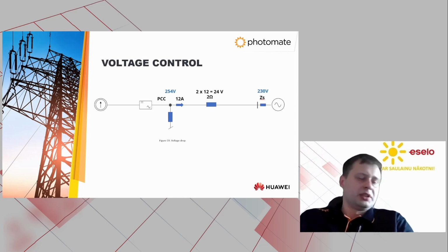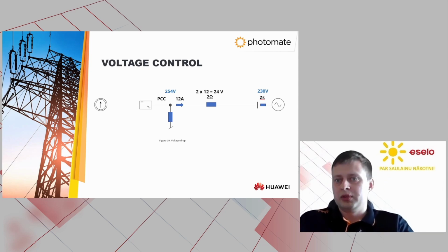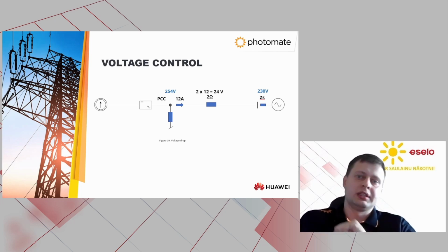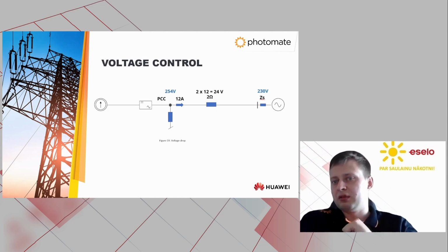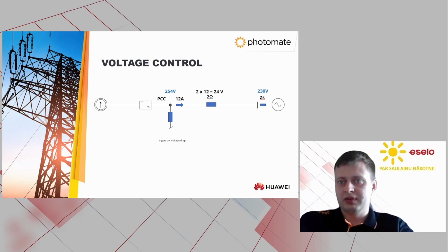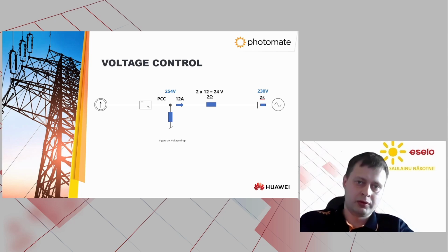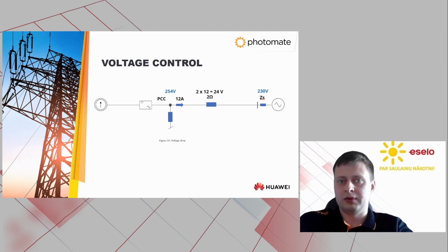It is a common misconception to think that the inverter is responsible for raising the voltage of the grid. However, in reality, the inverter works within the voltage range which is set by the transformer station plus any voltage drop along the cable. As shown in figure 19, when the inverter is trying to push 12 amps of current through a cable which has a resistance of 2 ohms, it gets 24 volts of voltage drop. If you add 230 volts plus 24 volts of drop on the cable, you get 254 volts on the terminals of the inverter.